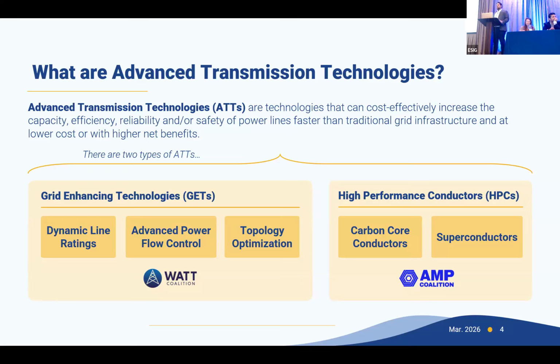On the AMP Coalition side, we focus primarily on new types of conductors. One category is carbon core conductors, which replace the traditional steel core with a carbon fiber or composite core that's lighter than steel, providing capacity and efficiency gains compared to more traditional conductors. Superconductors use specific metal alloys that are super-cooled, allowing power to be transferred with almost no losses.